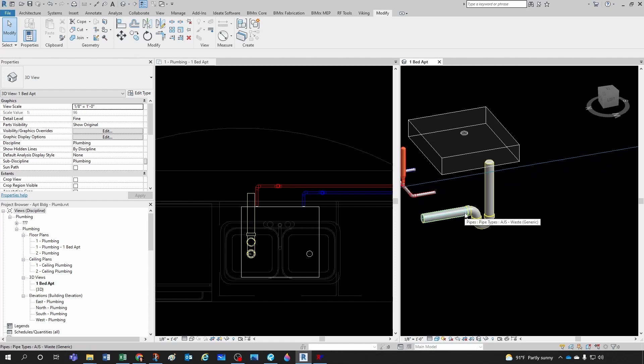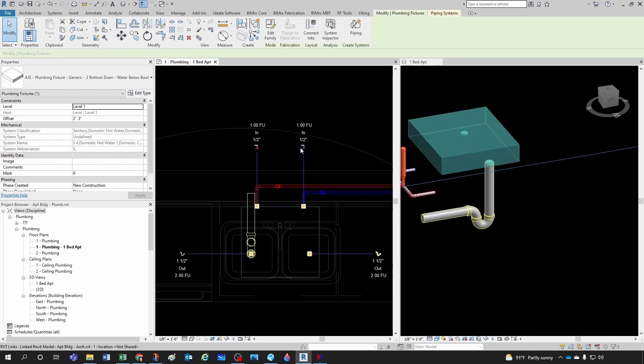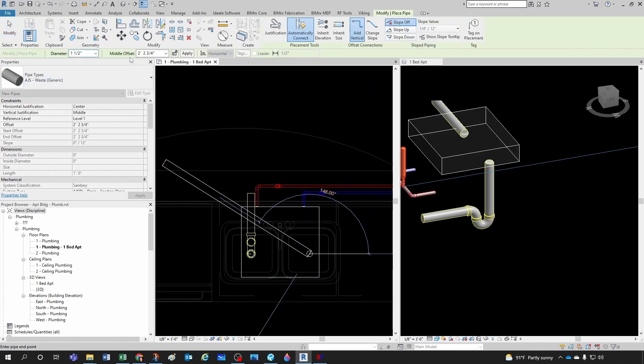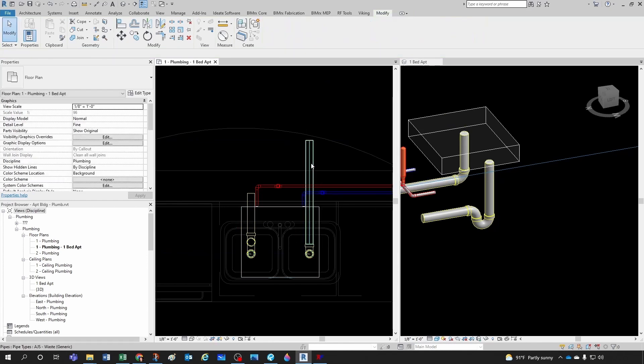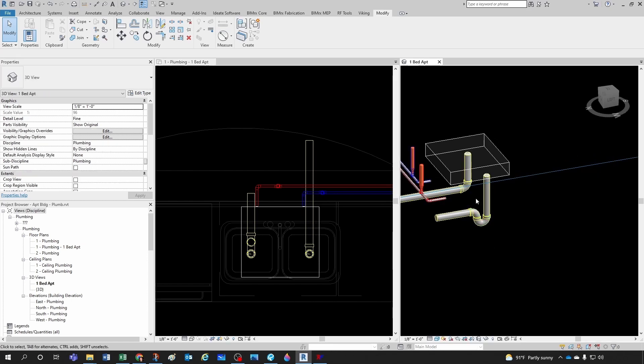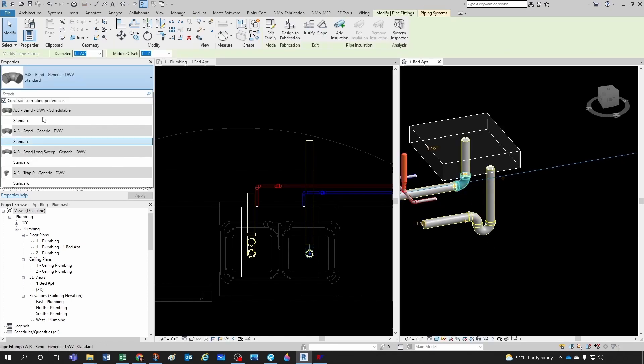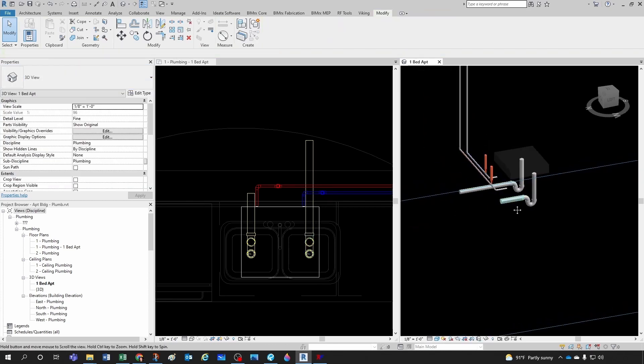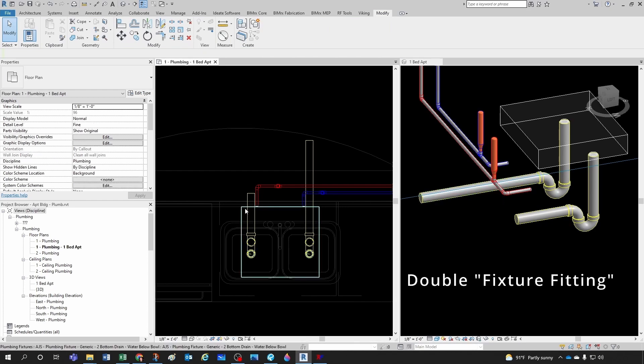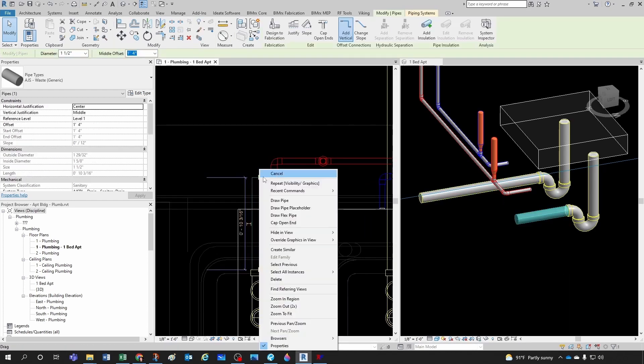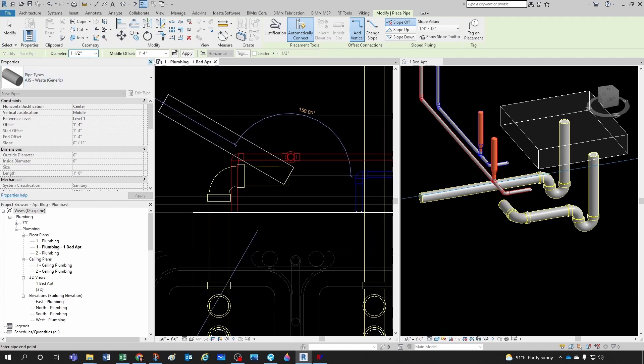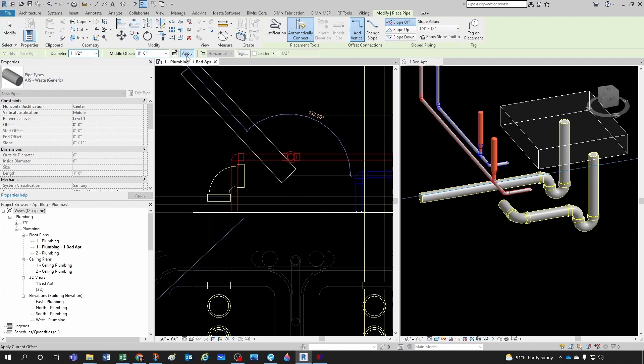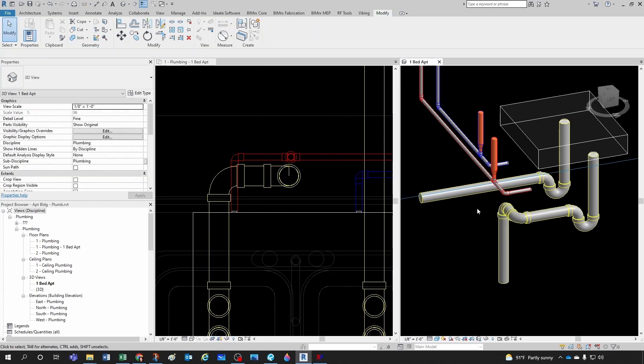We have our first P-trap. I'll do the same thing for the other drain — I believe I dropped it to around 2'-4". Sometimes I like to exaggerate the drop a little just so I don't run into trouble, then I adjust as needed. I select the elbow again and change it into a P-trap. I want to connect them both with a double sanitary tee on a vertical. To do that, I turn with an elbow and drop it down to 0 feet, hit Apply, and that introduces the drop.